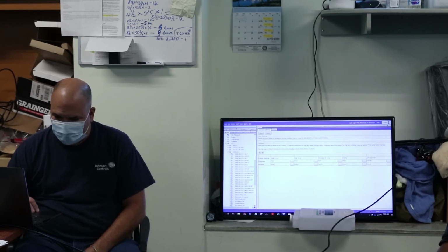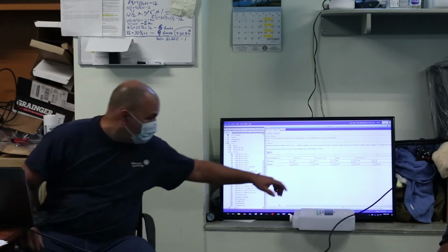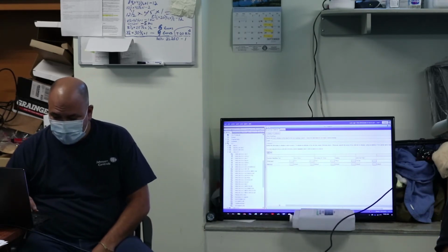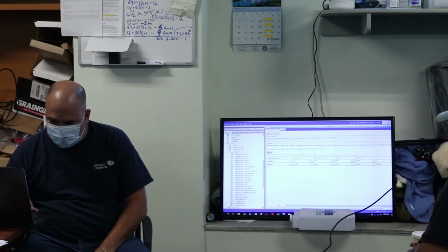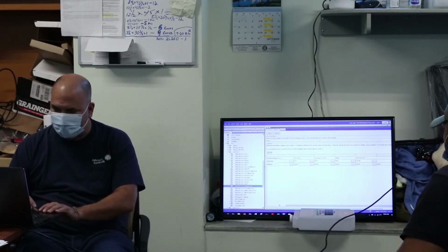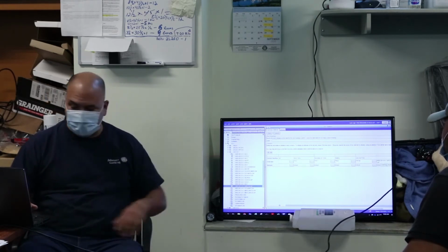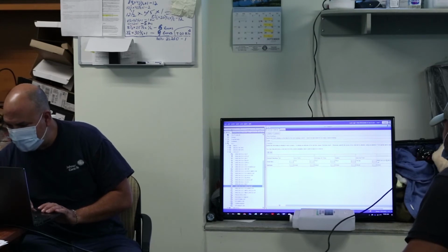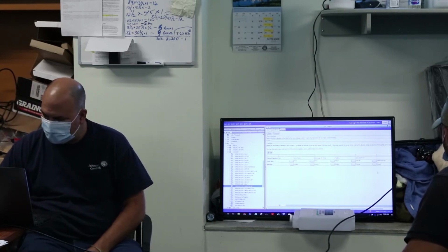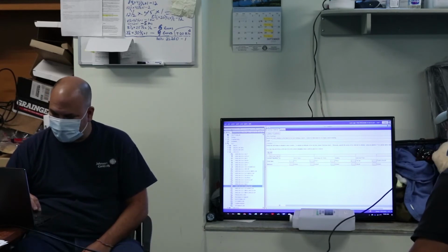So one way we could do that, we're going to add it in this column here. As you see, over on the other side we have a blank box. So we're going to choose the supply air set point, and I'm going to drag that over there. But now that would just be for that one specific VAV box. So how I'm going to edit it is I'm going to take out the prefix and put the asterisk in there. So that'll make it good for everything from that point down. Now I'm not going to edit it. I'm going to save that.